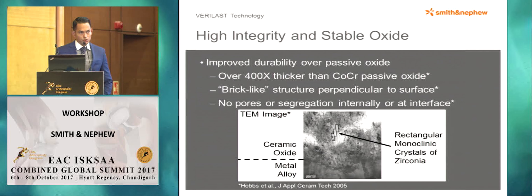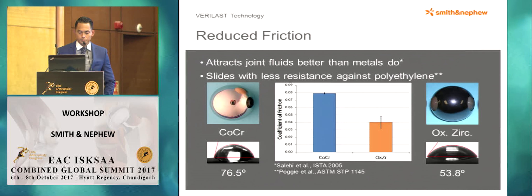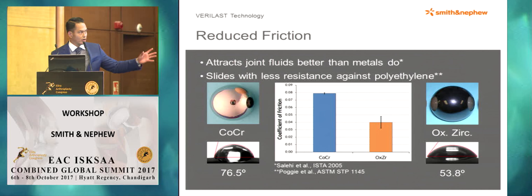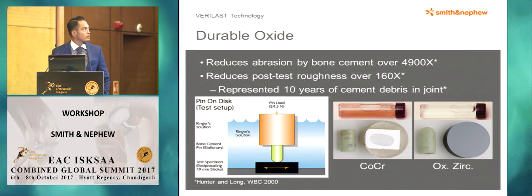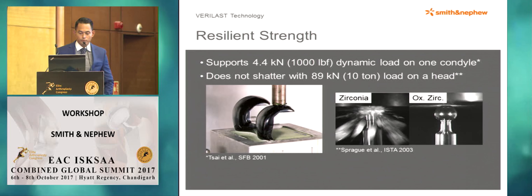This surface has improved durability over passive oxide — it's over 400 times thicker than cobalt chrome passive oxide. There's a brick-like structure, as shown in that picture, perpendicular to the surface. With regards to reduced friction, it attracts joint fluids better than metals, so there's less resistance when sliding against polyethylene compared to cobalt chrome, as that bar graph demonstrates. It reduces abrasion by bone cement by a factor of 4,900 times, and post-test roughness is over 160 times less. This represents 10 years of cement debris within the joint — so all very good advantages.